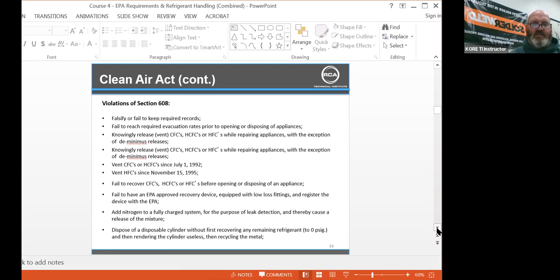Dispose of a disposable cylinder without first recovering any remaining refrigerant, and then rendering the cylinder useless and recycling the metal. You definitely want to make sure that wherever the branch is that you're at, you're recovering if you're doing any transfer, or you're taking your bottles to RSD or Air Cold. They'll handle that for you. You don't want to handle that. But get with your individual service managers and your branch managers on what they would like you to do.